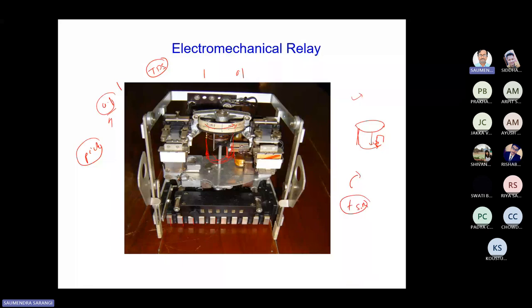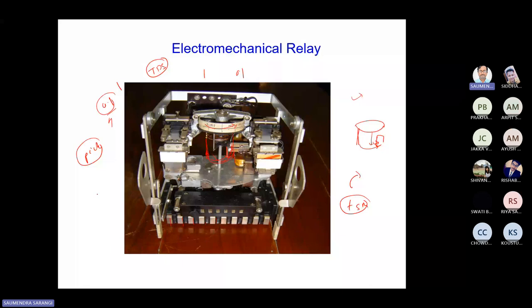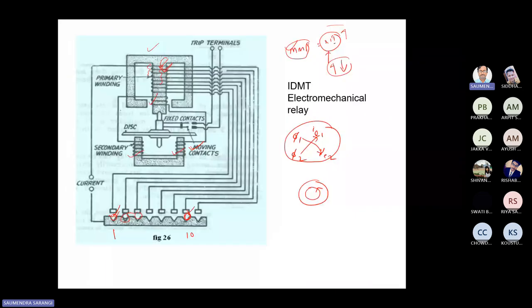And the pickup setting, if it varies, we have to see that it is called the pickup setting or plug setting. Okay, pickup setting and plug setting are two different points. Pickup setting is decided according to the load current. How about the plugs we are having? It is fixed. We may have a different pickup setting, but you are having the plug setting here. If you observe the different plugs available here, if you change the plugs, automatically this much current you have to operate.